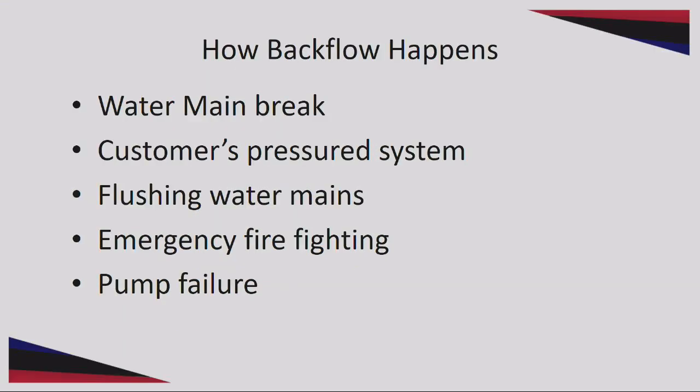These are a few of the ways you can have a backflow incident: main breaks, customers who have processes that are pressurized vessels, city staff flushing water mains, emergency firefighting, and pump failures. Some of these are planned. Obviously, if the city's out there flushing mains, we can plan that. If we're educated on backflow, we can understand what line pressure is and what business pressure is and manage this in a way that we don't cause backflow incidents. But if there's a fire or there's a line break, all bets are off.